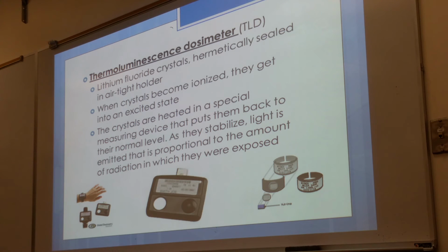Okay, thermoluminescent dosimeter, or TLD. Within the hermetically sealed plastic holder, you will find lithium fluoride crystals. When these crystals become ionized by radiation, they go into an excited state. So they're storing this X-ray energy until they are ready to be read at a later time.